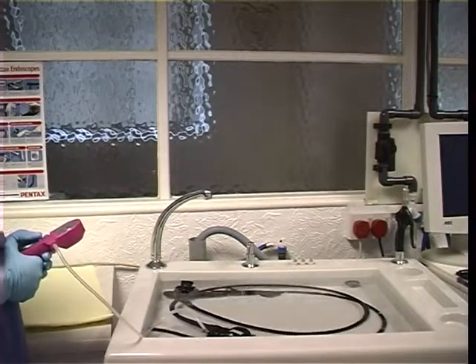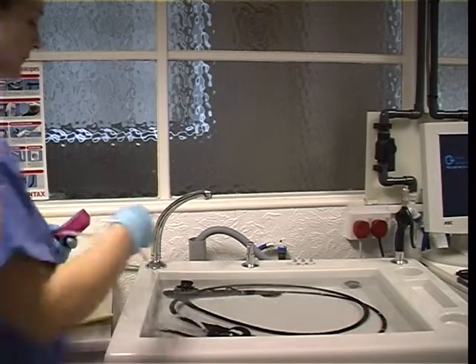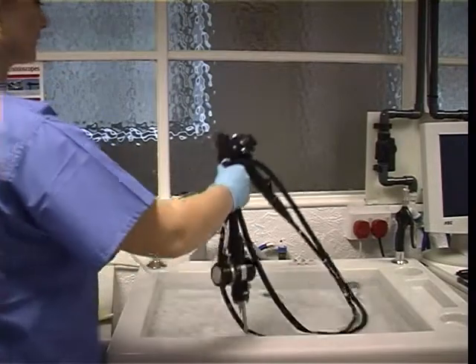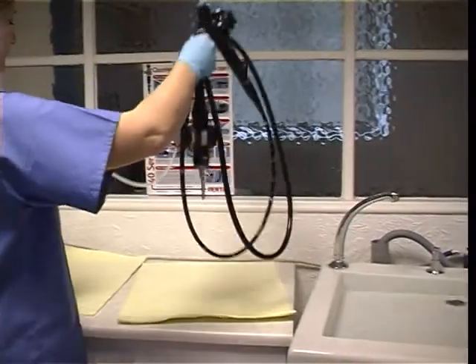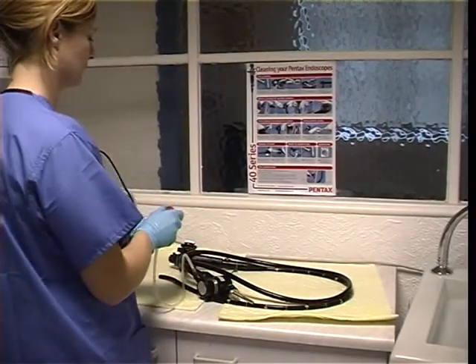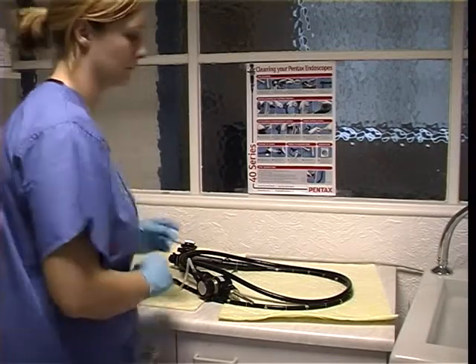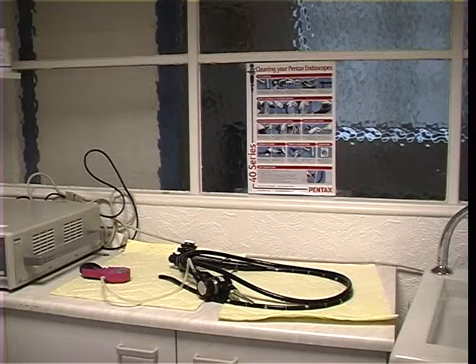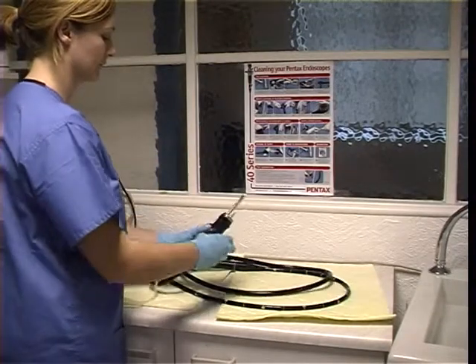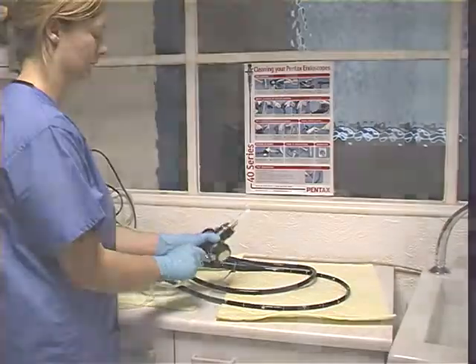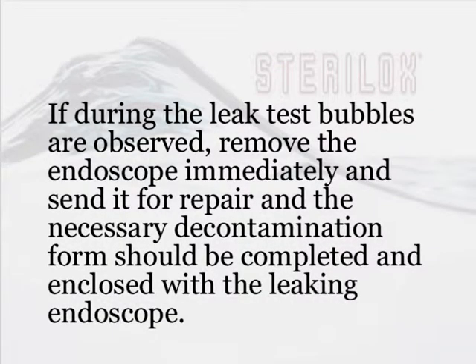When you are happy that the leak test is complete and successful, remove the endoscope from the water. You will then deflate the air from the leak tester. Warning: you must never deflate your leak tester while your endoscope is still immersed. Leave the leak tester attached to the endoscope for at least 30 seconds, remembering that the longer the endoscope is in length, the longer it may take for the air to be completely removed. By ensuring complete removal of residual air, it reduces the likelihood of your distal tip getting the famous sausage syndrome. Finally, detach the leak tester from the endoscope. If during the leak test air bubbles are observed, remove the endoscope immediately and send for repair, and the necessary decontamination form should be completed and enclosed with the leaking endoscope. You are now ready to perform your documented manual cleaning procedure.